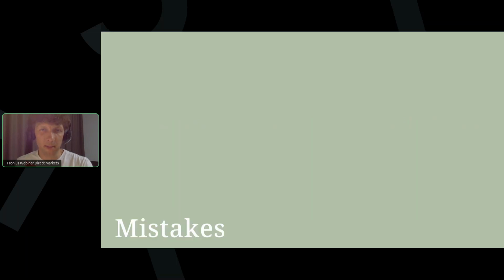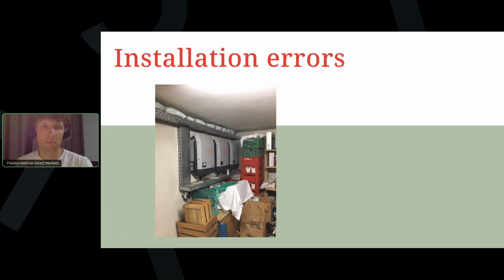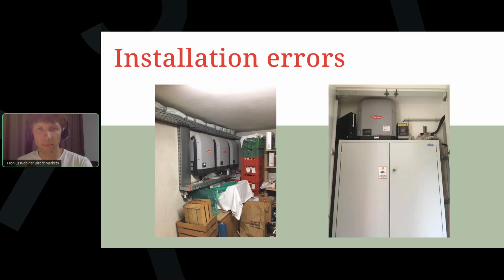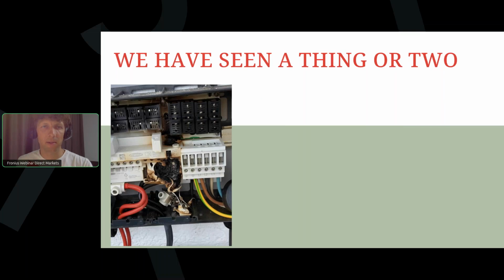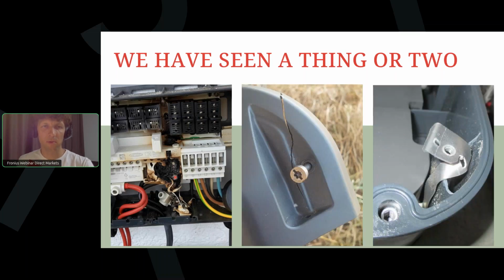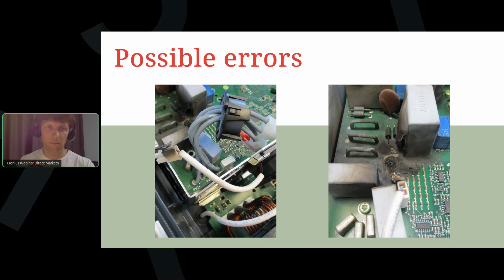There are some common mistakes. Usually it's installation problems, not leaving enough space, so inverters overheat. Sometimes mounting is not tight enough, or tightened too much, and you can damage the inverter. Also sometimes there's bad installation on the DC or AC side, and if inverters are installed without SPDs, this can cause problems inside the inverter.